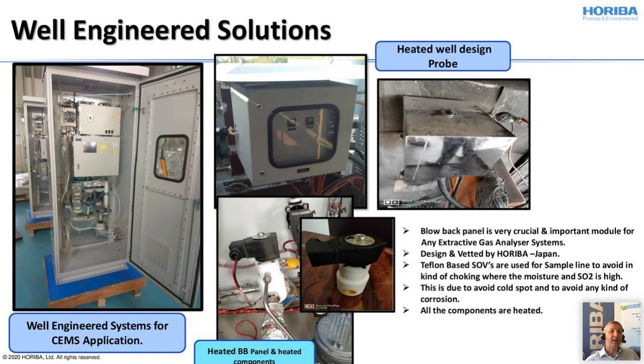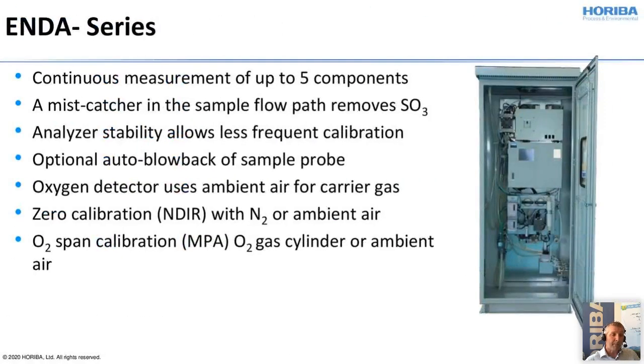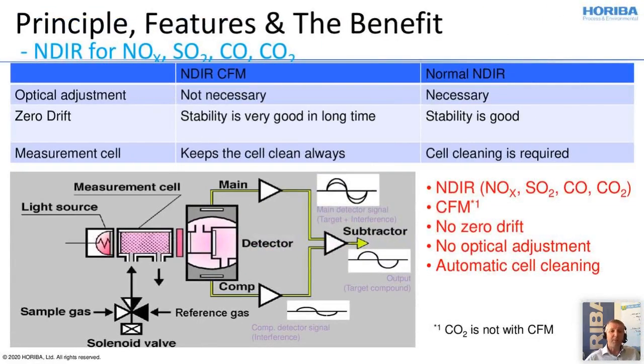The ENDA-Series instruments can measure up to 5 components in one. We have a mist catcher in the sample line to remove the SO3, because nobody wants to have sulfuric acid in their analyzer. It will damage everything. And you know, SO3 plus H2O will result in sulfuric acid, which needs to be avoided. For all the measurement technologies we have, for zero calibration we are using nitrogen or ambient air. We have oxygen span calibration also with ambient air, or with the oxygen gas cylinder, as will be described in the next slides.